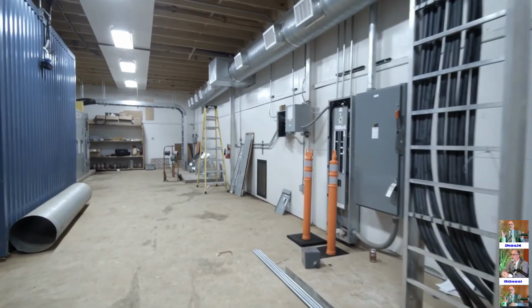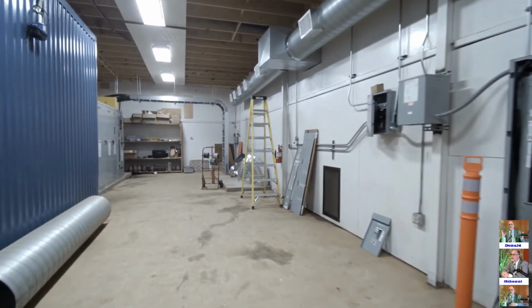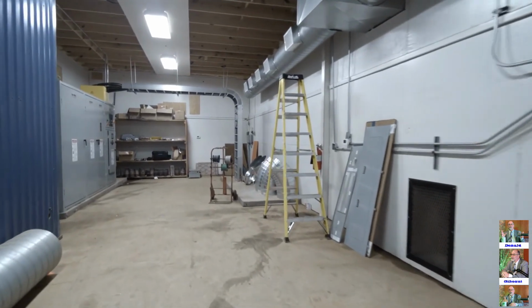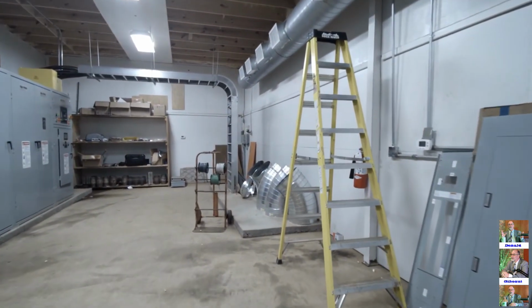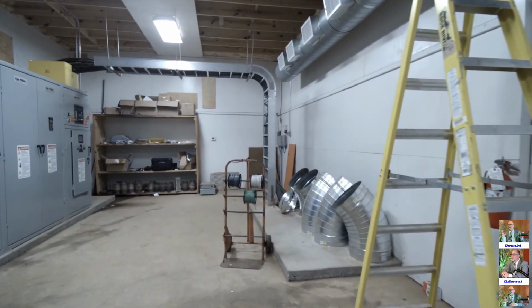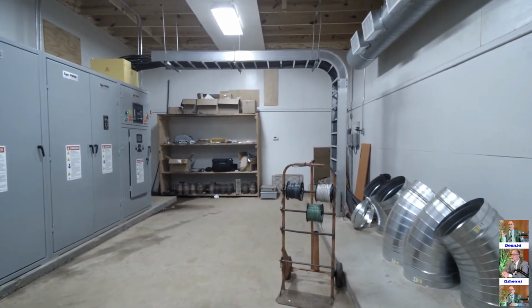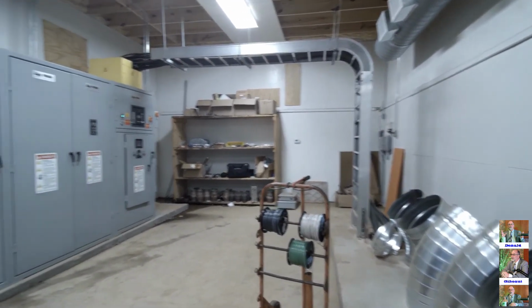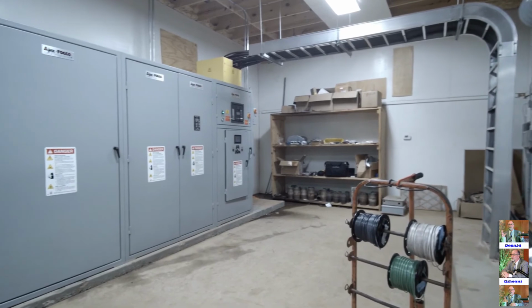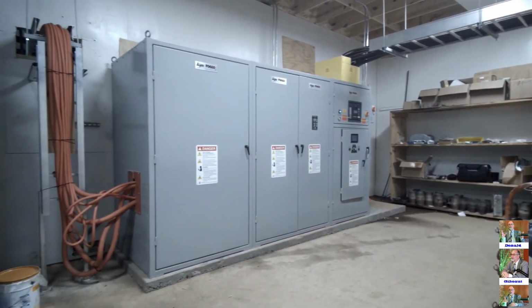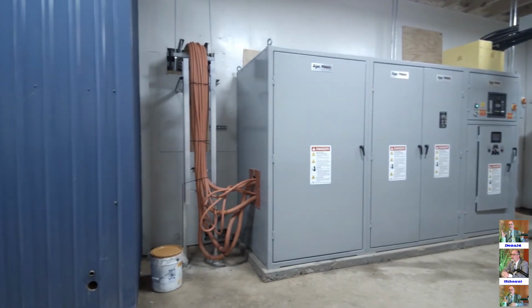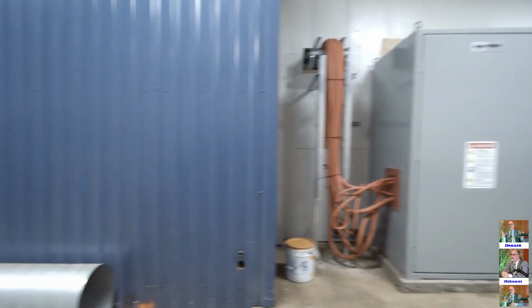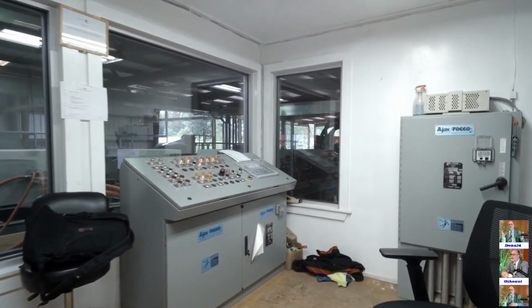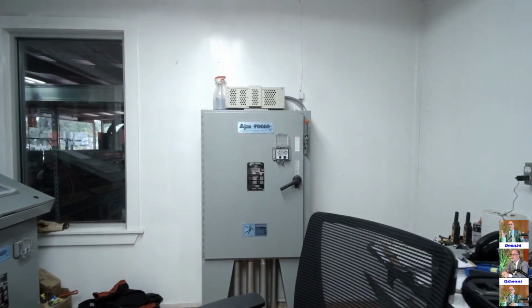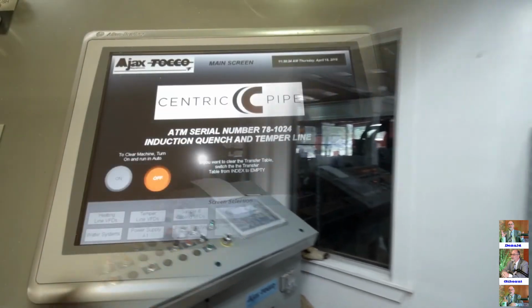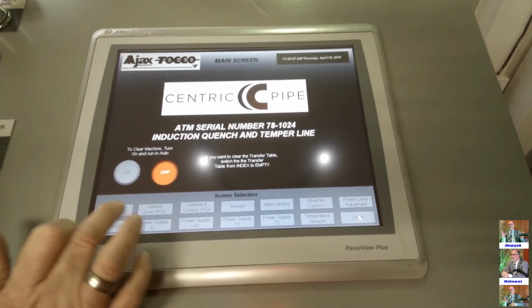This is your incoming power from the transformers we saw outside. Some ancillary disconnects there, breakers. This is the austenitized 2 power supply. They're 2,500 kilowatts. They have harmonic filters mounted in the cabinet themselves, and the components of that harmonic filter are water cooled by the cooling water of the power supply. This is a transistorized IGBT power supply. Here's the control room, the little blue room to the right of the austenitize I mentioned. It has HMI and manual controls.